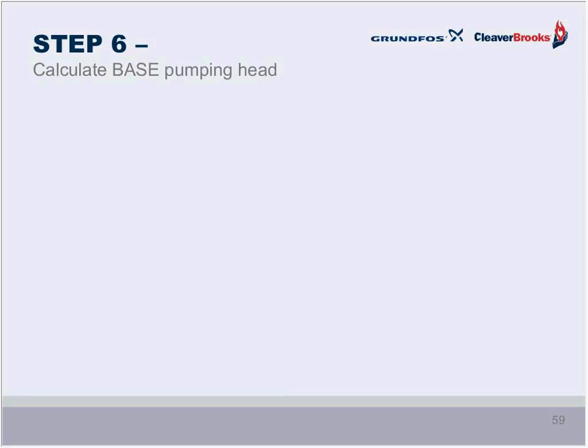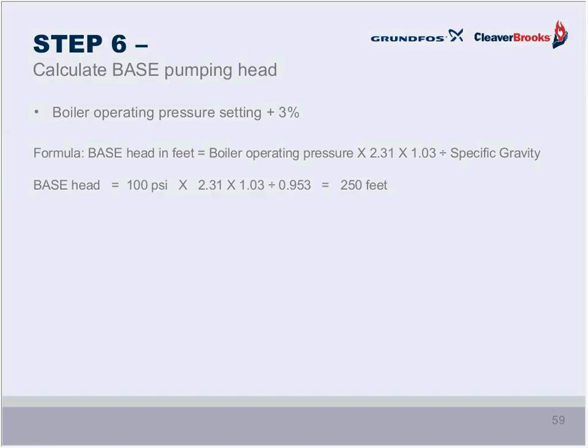We have to calculate the base pumping head. We have to take the boiler operating pressure plus 3%, and there's a formula that we have to follow, taking the base head and multiplying the pressure of 100 psi times 2.31 to convert to feet, times a 1.03 safety pressure setting, and then we divide that by specific gravity. That all comes out to 250 feet of head.